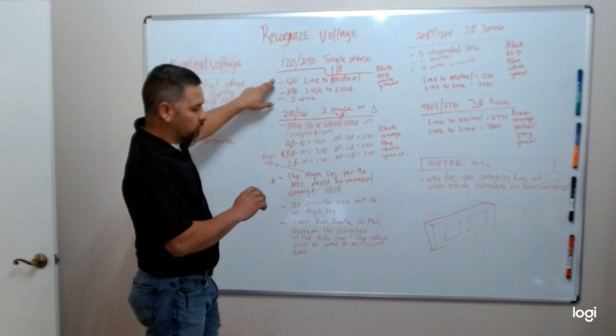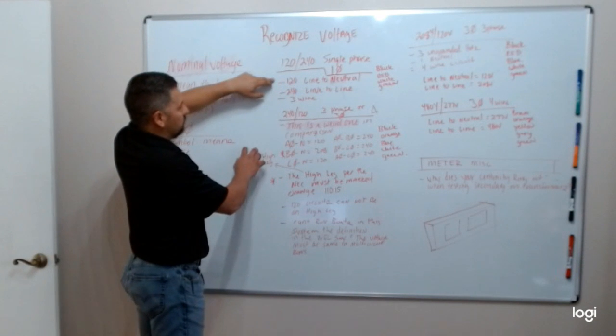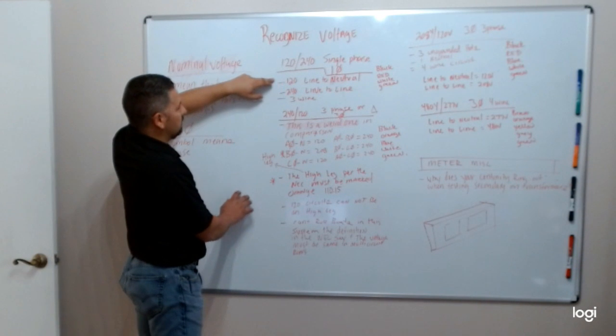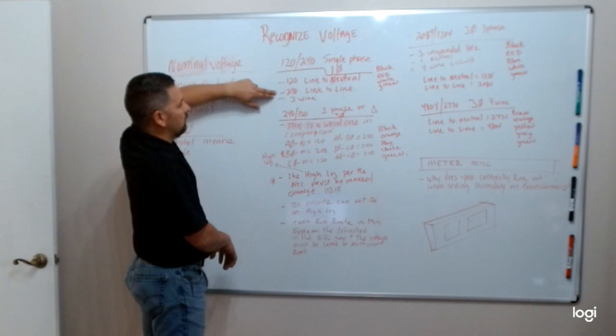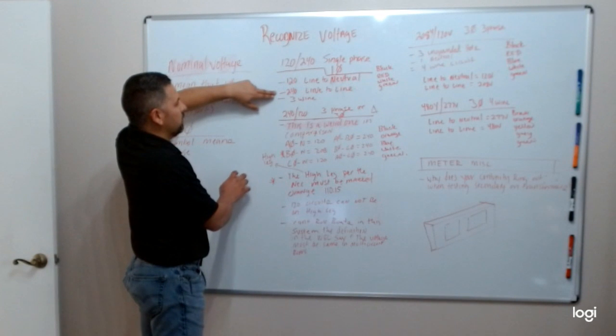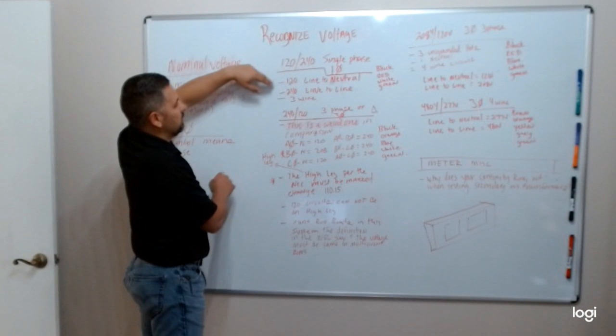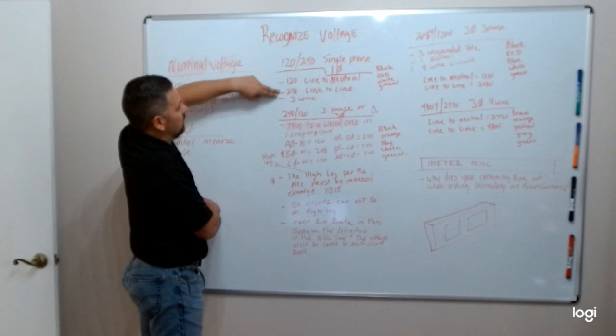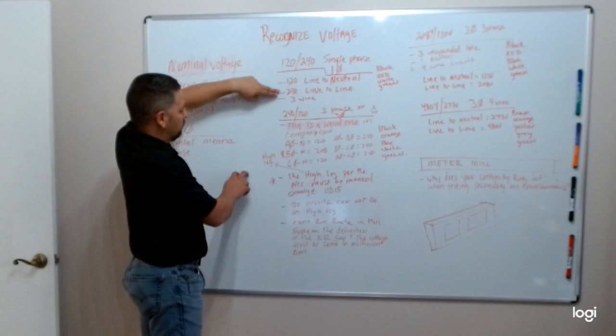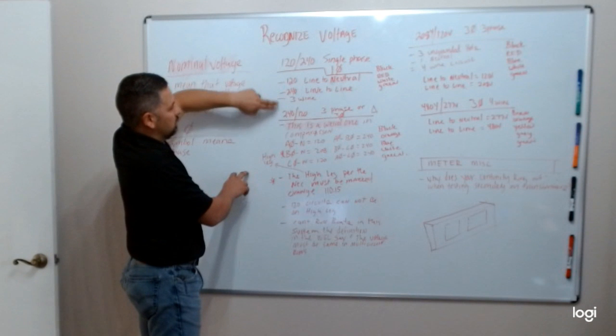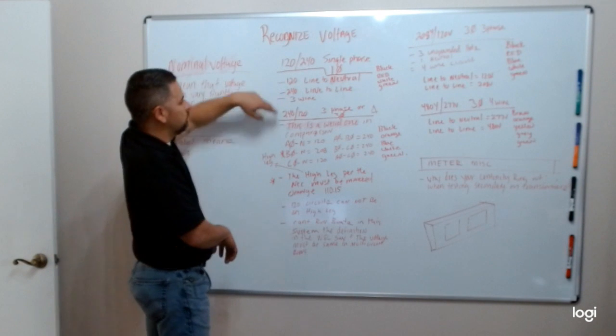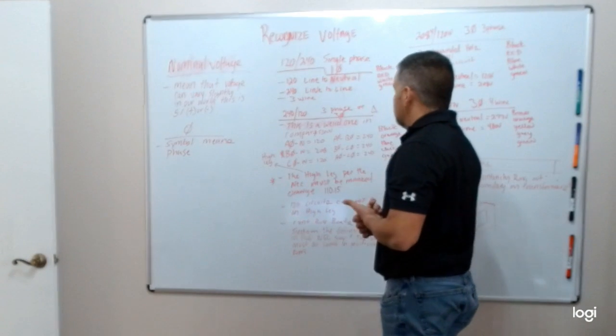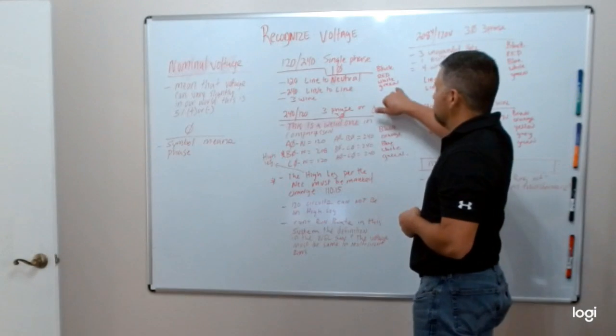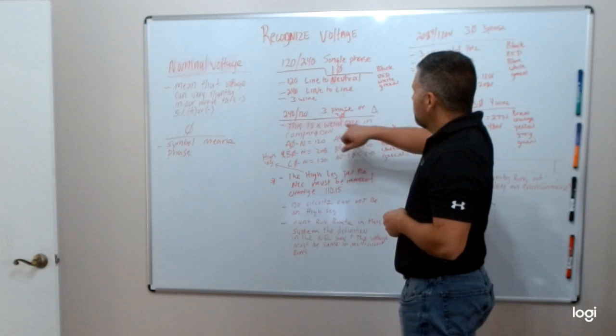From line to neutral, you should have 120 on A, B, and C. On line to line, you should have 240, or I guess not A, B, and C, A and B, 240 between A and B. It's a three-wire system, so meaning you have a hot, a neutral, and a ground. And then obviously your green for your ground.